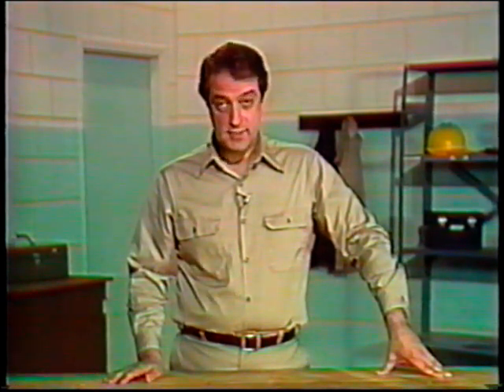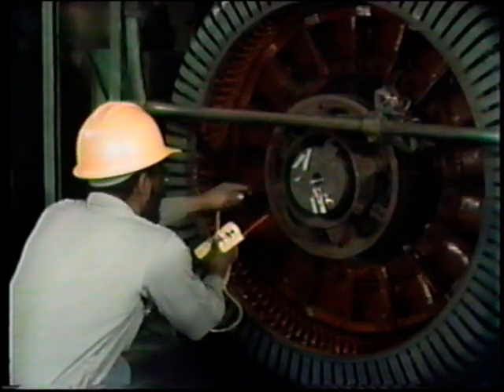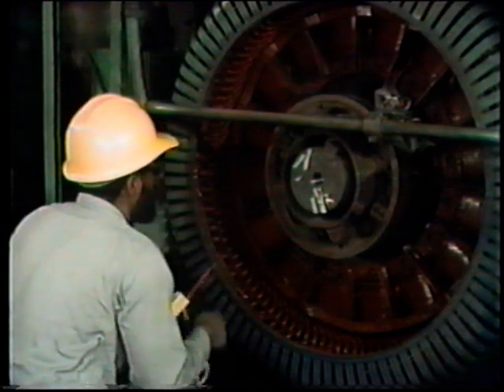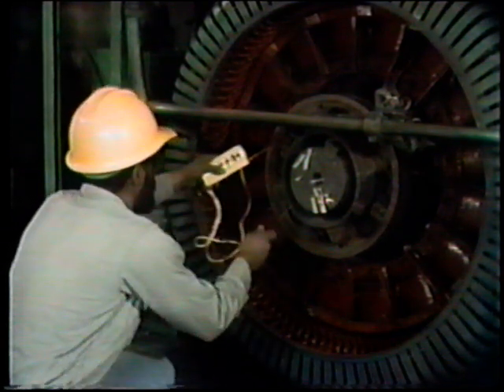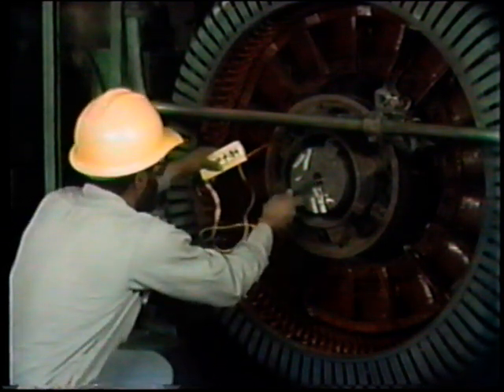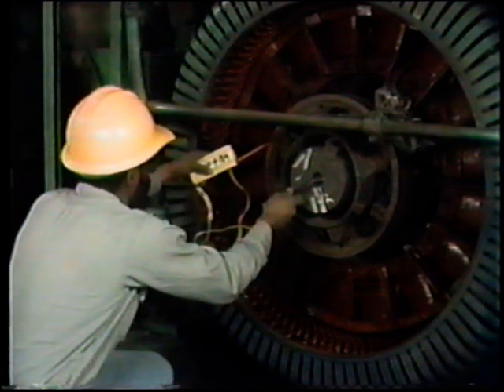A common preventive maintenance test for a synchronous motor is the insulation test. This test is usually done on both the stator and the rotor. In this demonstration, we're going to test the rotor. The instrument used for this test is a meg-ohm meter. Before beginning an insulation test, double-check to make sure the motor is tagged out according to plant procedures, and make sure it's de-energized. Then lift the brushes to isolate the rotor from its DC power supply.